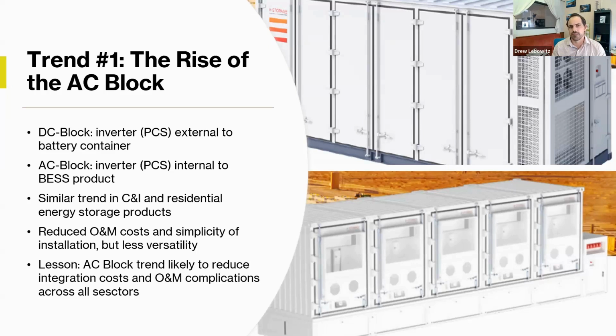I wouldn't say there's a definitive advantage to AC block or DC block. Really most of them are very similar technology. You're still going through an inverter, still going into and out of the DC block. So from what I've seen, there isn't a huge difference on that. I would say the difference is that there's a little less complication in the way an AC block system works, because they would provide a performance guarantee right at the terminals of the battery, which is the AC terminals.